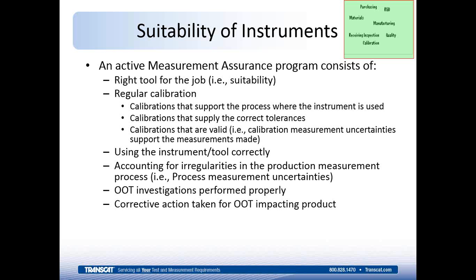So now I'm going to give you some more examples of how instrumentation measurements and incorrect readings can cause false accept or false reject in the production process. So let's say you're an engineer that needs to make a measurement of a solution used to treat the product. And the process is at 350 degrees Celsius, and your acceptance tolerance of the process for that temperature being applied to the solution is within 2 degrees. Now you've got to figure out an instrument that's suitable for the measurement.